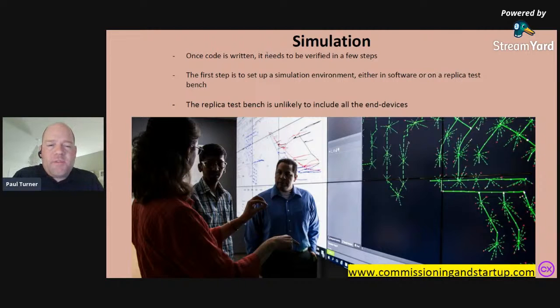So let's go through some of the steps to get ready for commissioning. In advance, during the design phase, once the software is written, you definitely want to go through a simulation process to confirm that what's programmed is actually going to function by the time it gets into the hardware. So through simulation on a test bench, what the test bench could be a set of replica hardware, a replica PLC to kind of replicate the hardware. With the software programmed in there, you go through all the process control functions, all the complex logic, and you confirm generally that the software is going to function correctly before it gets into the field.